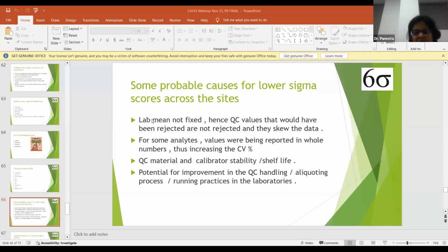If at 20 points you fix the provisional mean, you work on that for 60 points. Look at the data again. You might get a broader SD in that case. That might be helpful. So just don't fix the mean on 20 points. Fix on 20, review at 60, review at 90 again. And put this in your SOP that you will review at 60 points or 90 points.